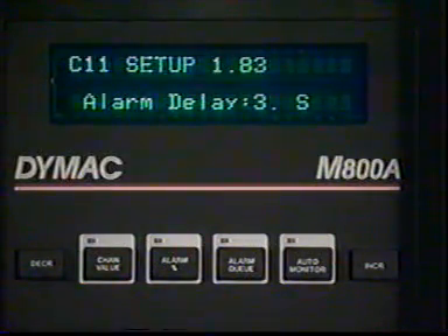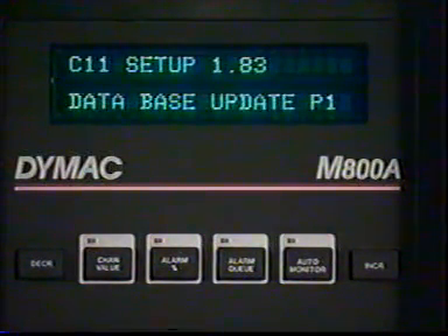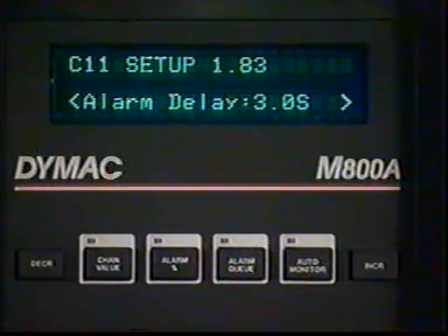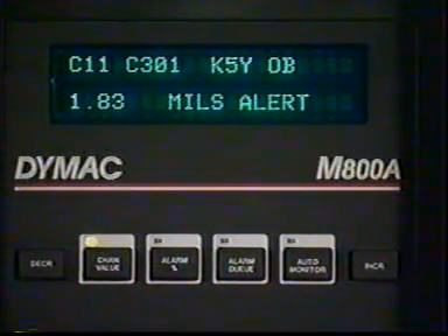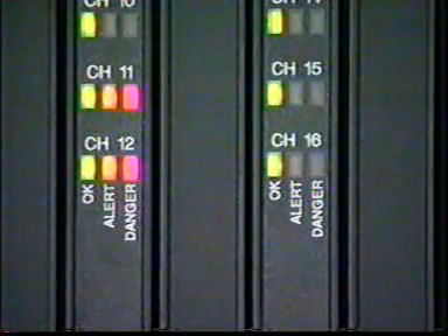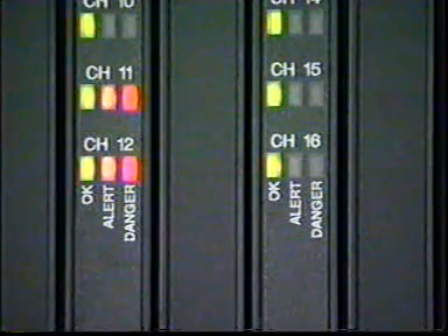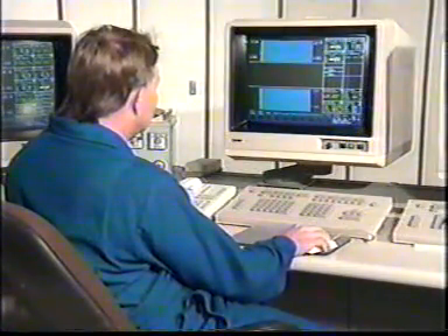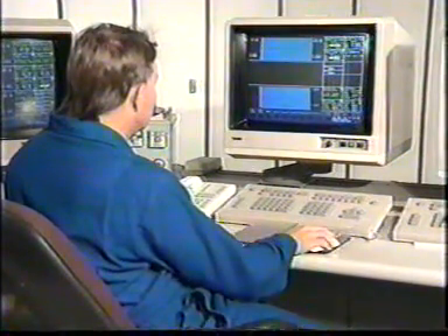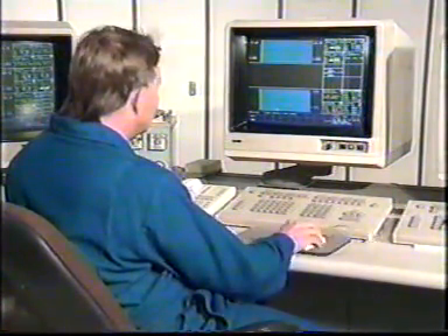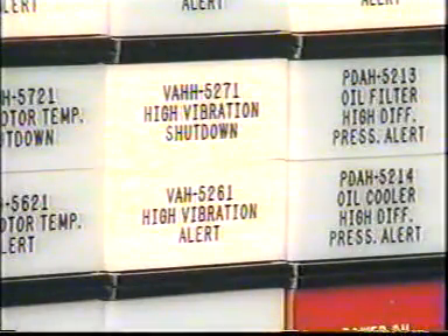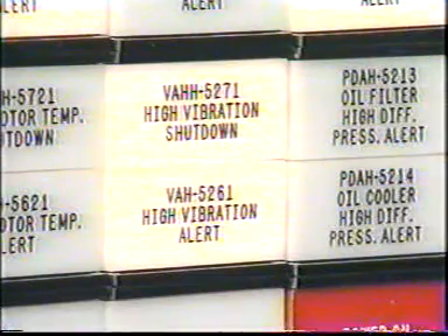Alarms and warnings can be established with or without delays. Sometimes vibration may be due to process problems. Operations may be able to correct the problem before machine damage occurs. Or the vibration may only be a problem if it continues over time. Many monitors provide two levels of vibration alarms. The first, or high-level alarm, warns operators of a change in vibration levels. In most cases, this level is set low enough to allow the machine to continue to operate while operators and maintenance personnel try to find the cause. A second, or high-high alarm, warns personnel of impending vibration damage if corrective actions are not immediately taken.